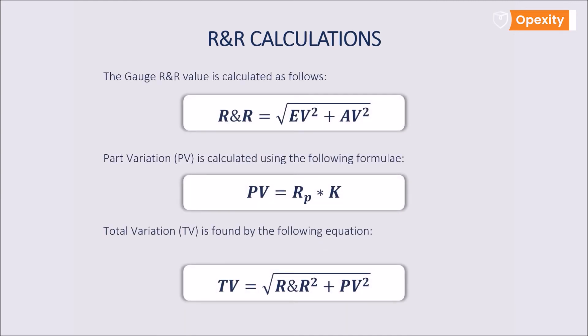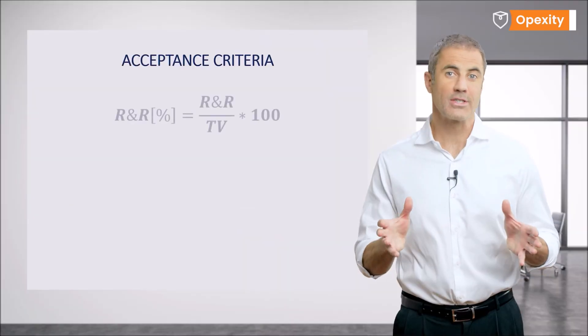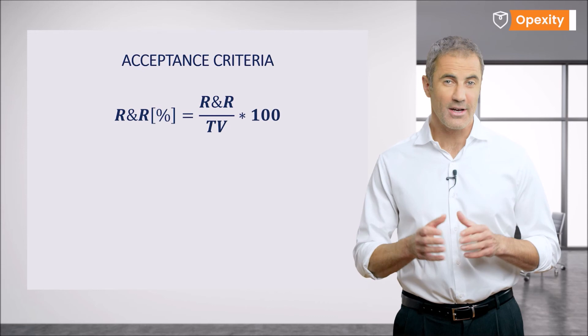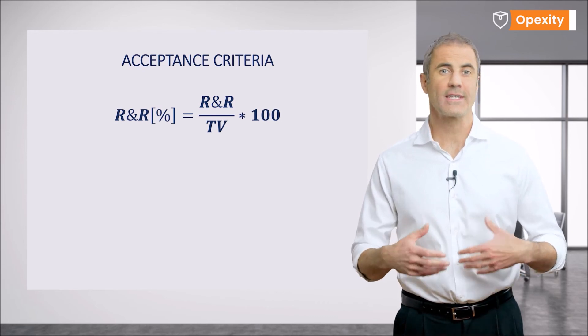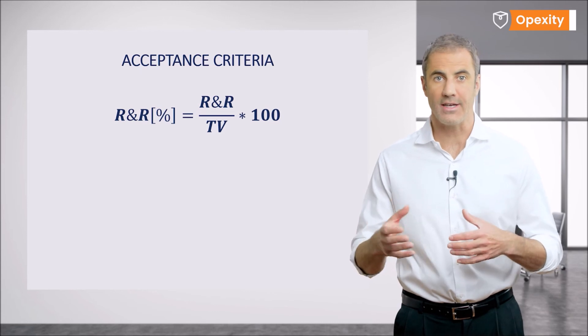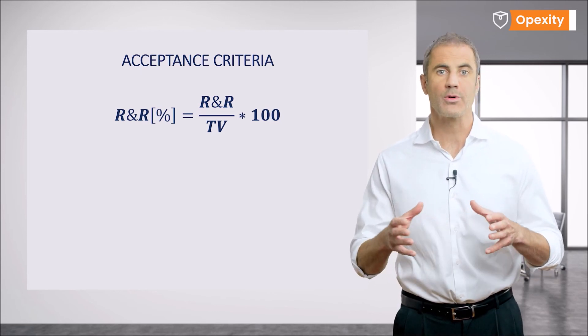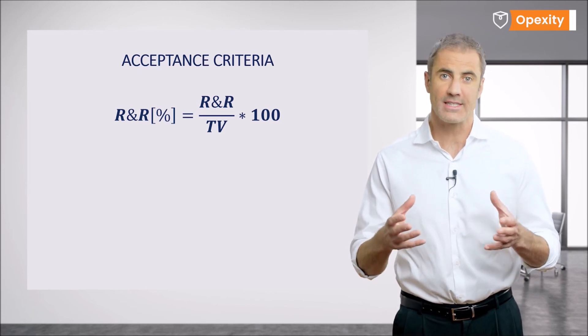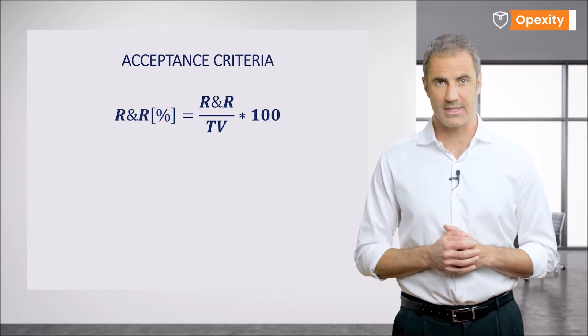Finally, we can calculate the output parameters for the measurement system that is repeatability and reproducibility R&R, part variation PV, and total variation TV. Now it's time to make an assessment. For this purpose, it is useful to calculate R&R percentage value as a ratio of R&R to TV in percentage, which will give us the opportunity to use the acceptance criteria of the measurement system.